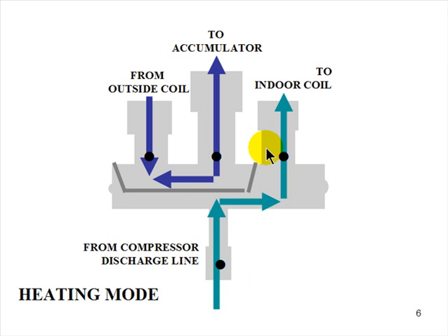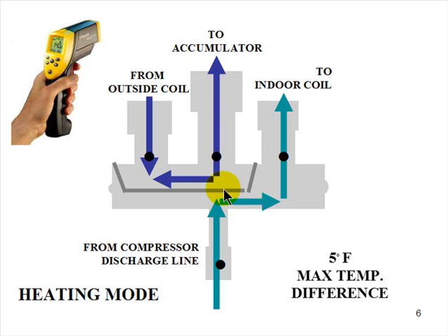This is also from Trane, my friends at Trane, and this is a good test you can make on a reversing valve to find out whether or not it did complete its slide and whether or not there is a leak somewhere. If you're in this position where the indoor coil is receiving the hot gas, then you take your laser thermometer, and that's a perfect application for it, and you check the discharge line going in, and you check the line going out to the indoor coil.